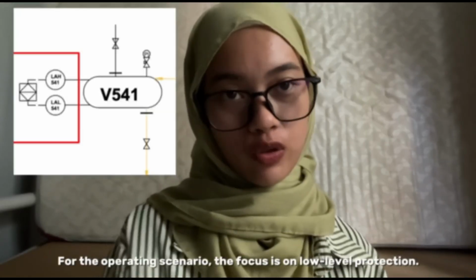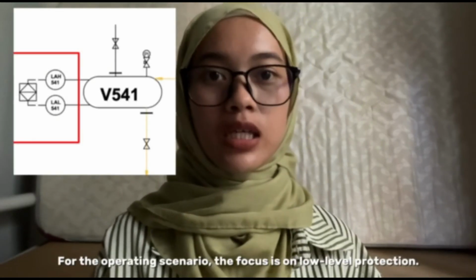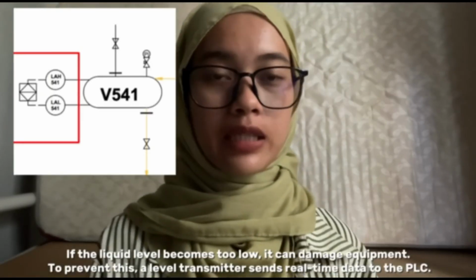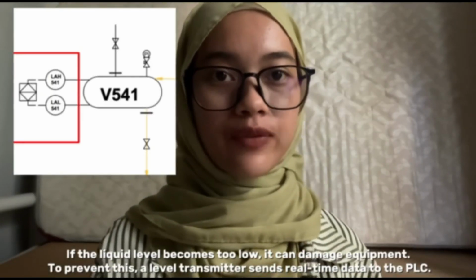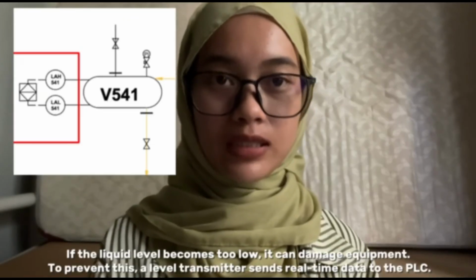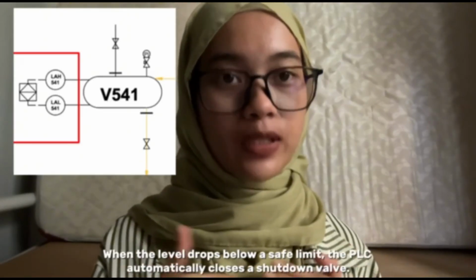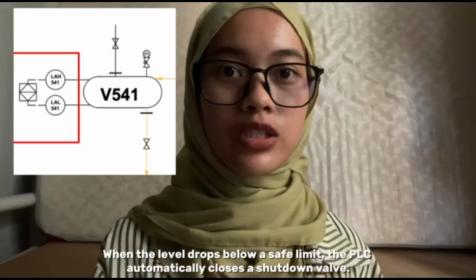For the operating scenario, the focus is on the low level protection. If the liquid level becomes too low, it can damage the equipment. To prevent this, a level transmitter sends real-time data to the PLC. When the level drops below the safe limit, the PLC automatically closes a shutdown valve.